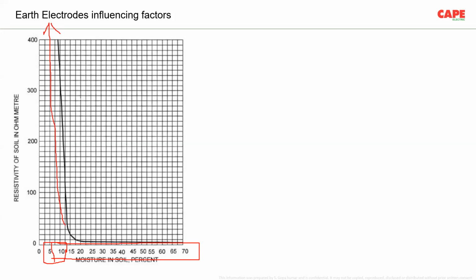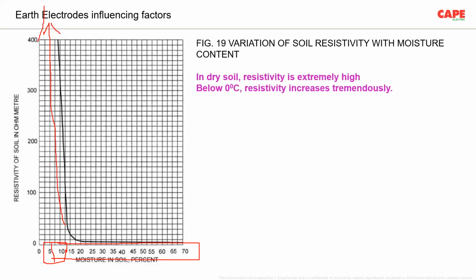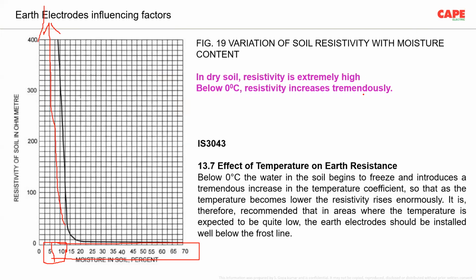If the moisture is zero, of course, nobody knows what the peak value is. So moisture is an important factor in soil resistivity. In dry soil, resistivity is extremely high. How high? Probably 10,000 ohm meter. Below 0 degrees centigrade, resistivity increases tremendously.